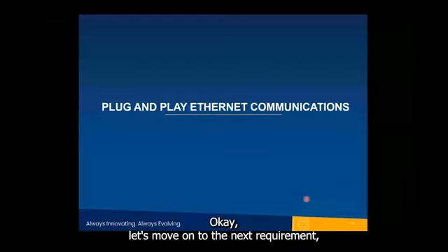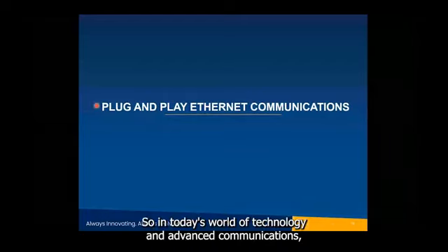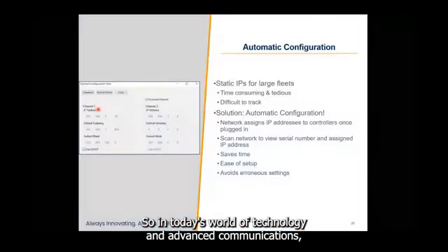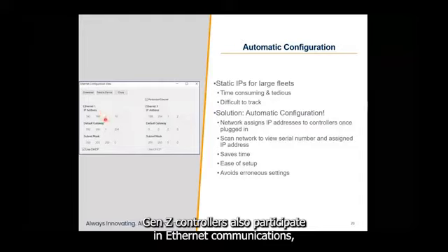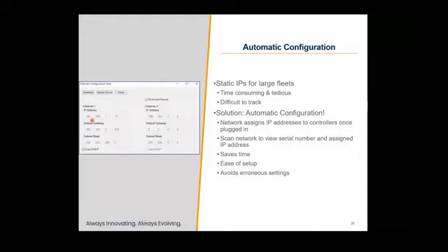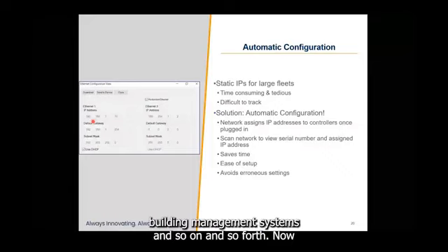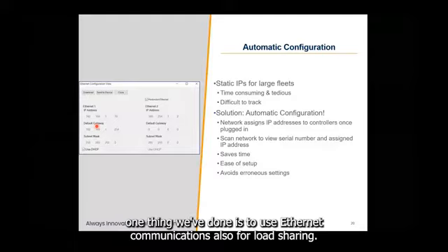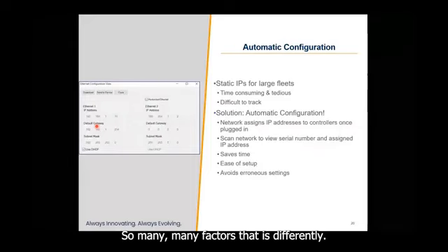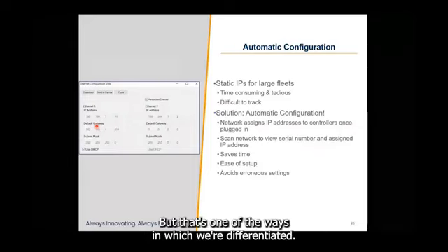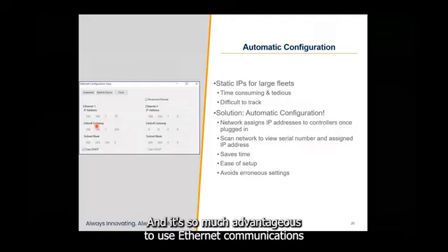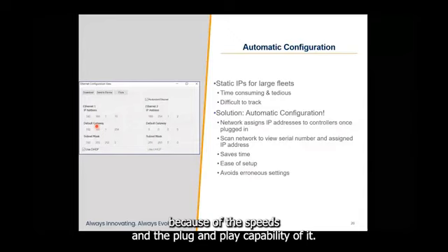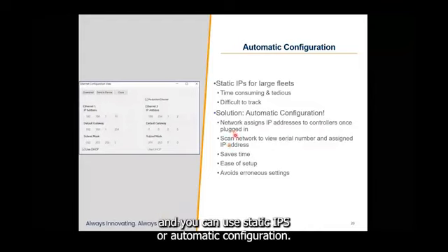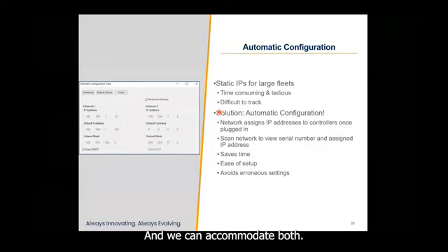Okay, let's move on to the next requirement, which is plug and play communications. In today's world of technology and advanced communications, genset controllers also participate in Ethernet communications, the Internet of Things, building management systems, and so on and so forth. Now, one thing we've done is to use Ethernet communications also for load sharing. Many manufacturers do this differently, but that's one of the ways in which we're differentiated. And it's so advantageous to use Ethernet communications because of the speeds and the plug and play capability of it. Now, there are two ways you can do Ethernet communications: you can use static IPs or automatic configuration, and we can accommodate both.